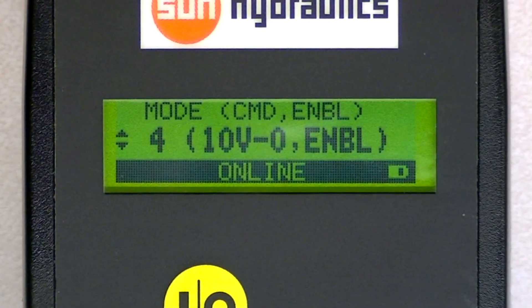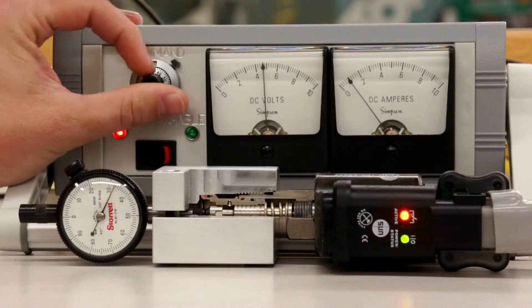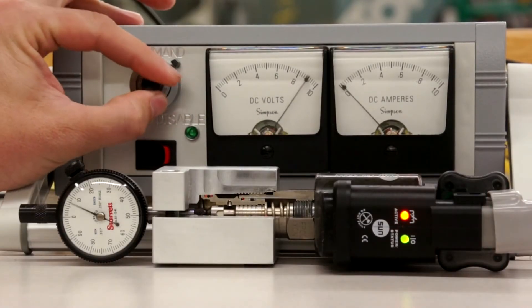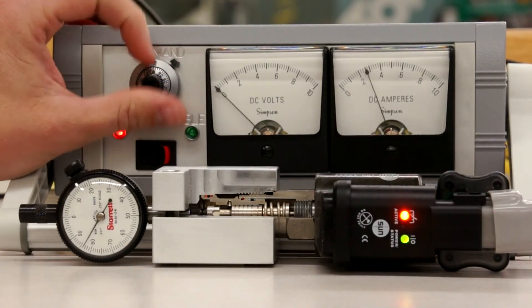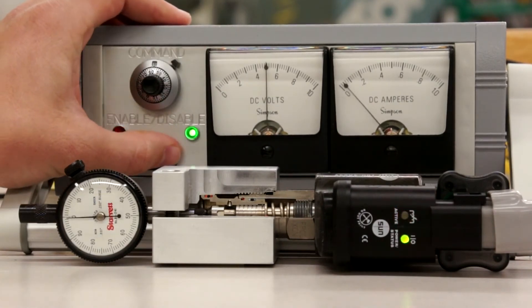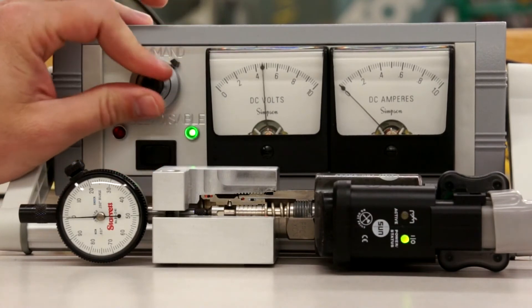Mode 4 is the same as mode 3, except it is inversed. So as we sweep the input from 0 to 10 volts, 10 volts will give us our minimum output, and 0 volts will give us our maximum output. If the enable is turned off, you will disable the output.